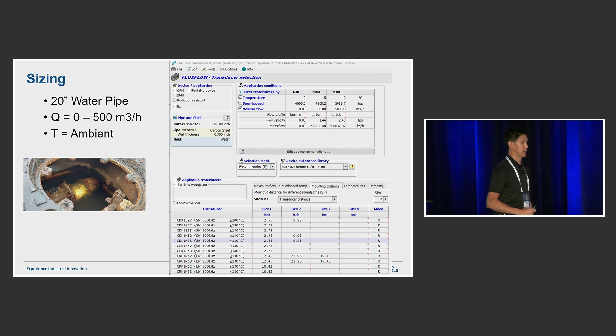So a quick example, again a bit of a chart. This is a 20-inch water pipe with a flow rate of 0 to 500 cubic meters per hour, and this is sort of what we would typically do for the sizing. There are a lot of things to look at, but you'll see here a bunch of transducers listed, and from there we decide which ones are a good fit. We also look at the SP number, which tells us how many paths.